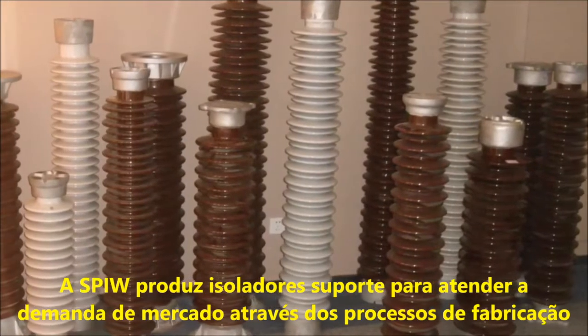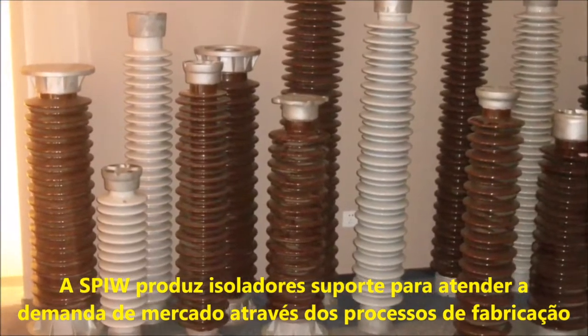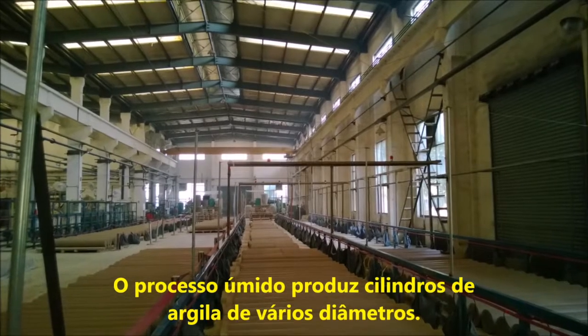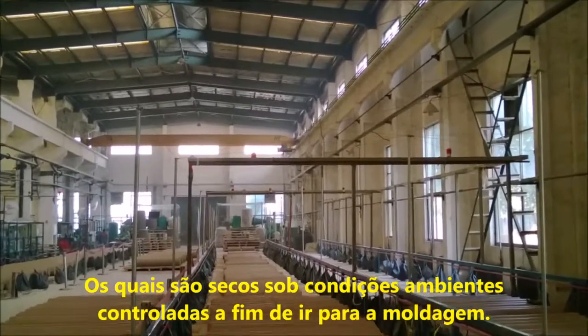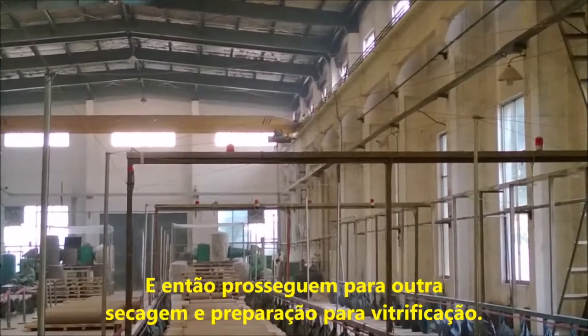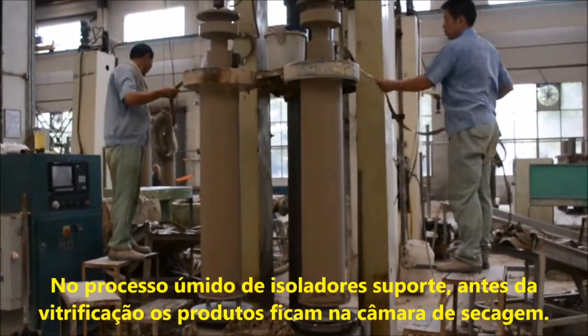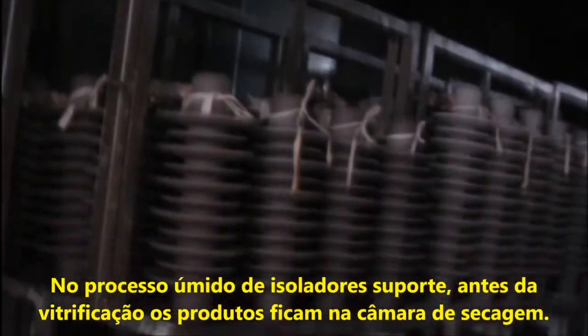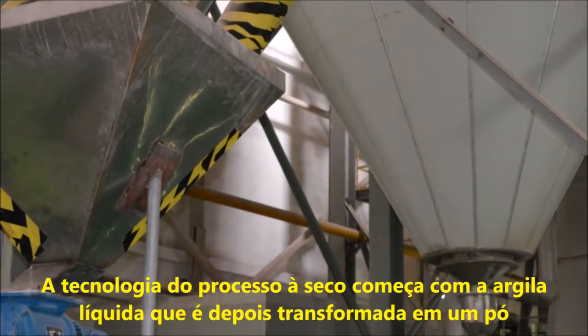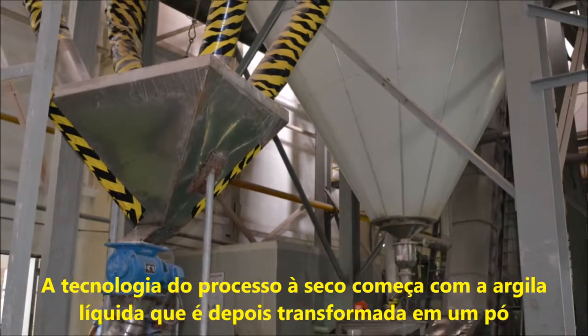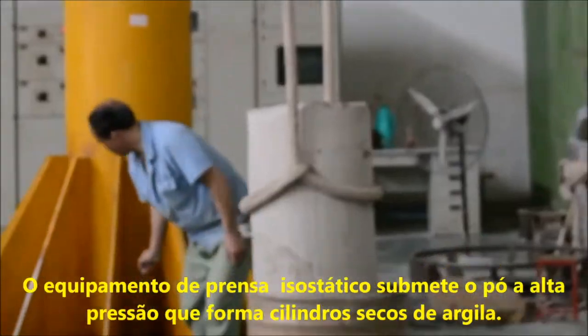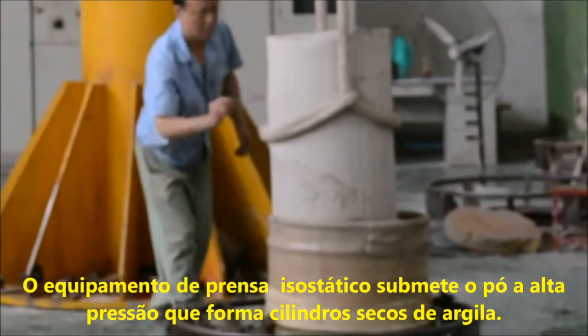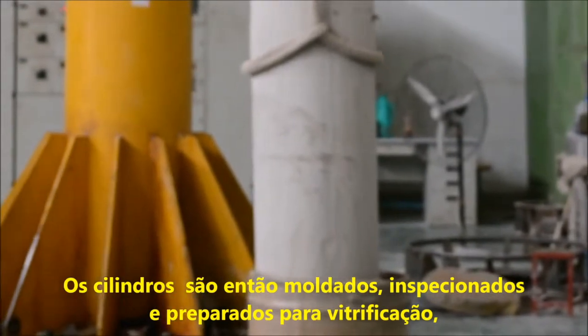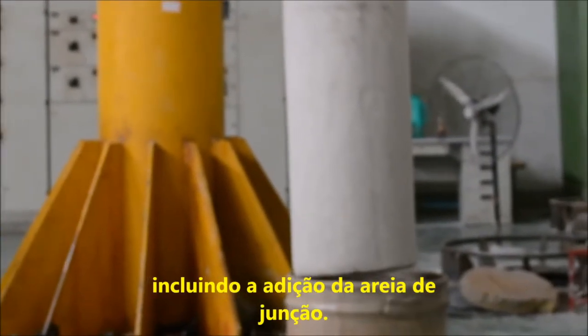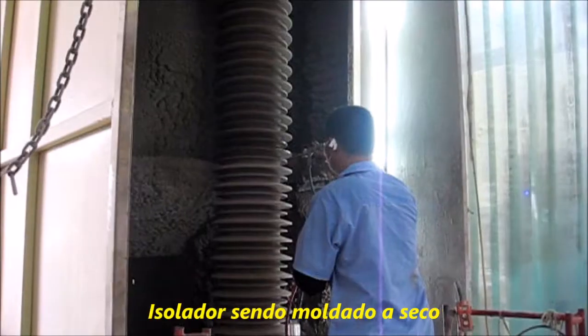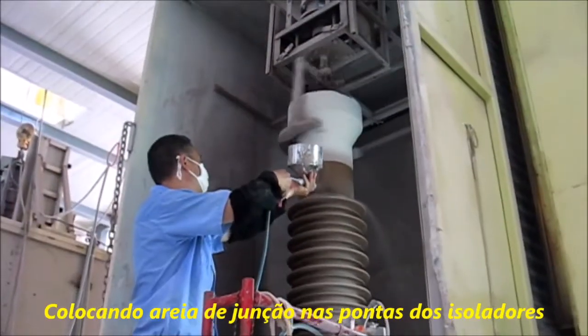SPIW produces station post insulators to meet the market demand, with both the wet forming process and the dry isostatic process. The wet process produces pugs of varying diameters, which are dried under controlled conditions prior to the turning process, then proceed to further drying in preparation for glazing. Wet processing of post insulator. Before glazing wet forming products into the drying room, the dry forming technology starts with a slurry which is then processed into a dry powder through a technique known as spray drying. The isostatic pressing equipment places the powder under high pressure, which forms dry blanks. The blanks are then turned, inspected, and prepared for glazing, including the addition of the binding sand. Dry trimming. Glazing in wet or dry forming products. Binding on insulator ends with sand.